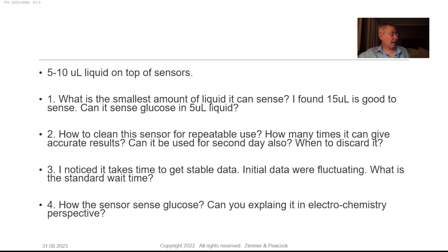How does the sensor sense glucose? Yeah, sure, I'll do that. So first of all, about your volume as well. We want to cover all the electrodes, so make sure that these very small volumes that you're using are actually covering all these electrodes. We tend to use 30 to 50 microliters. If you're getting away with 5 and 15, good to you. I'm surprised, but good for you.